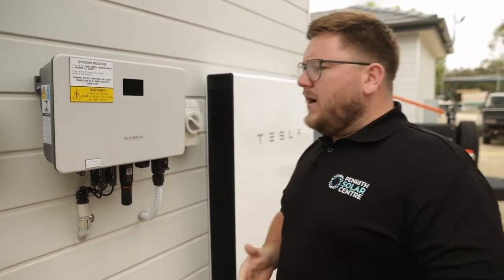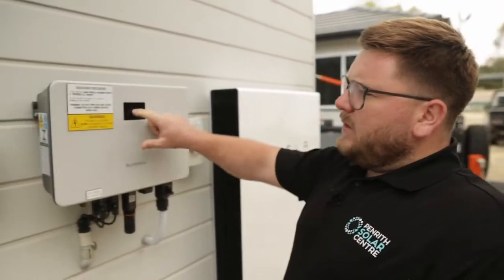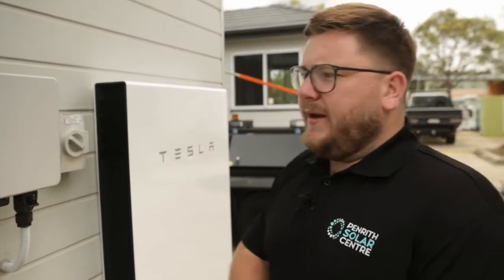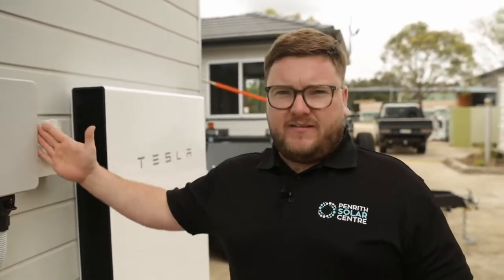You would run your tests as well, but for now we can safely assume that the inverter is shut down. On this particular inverter, the screen is completely de-energized. Before working on the inverter, it is important to test to make sure the inverter is de-energized.